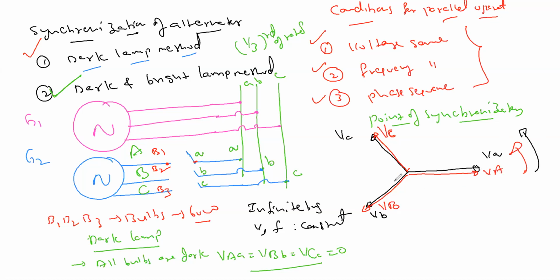And how do you change the phase sequence of the machine? Right now it is A, B, C sequence, we need A, C, B. By just reversing the rotation of the rotor, you can change the phase sequence of the generator. Mention this point: phase sequence of the machine can be changed by changing the rotation of the rotor. That was asked once in GATE.